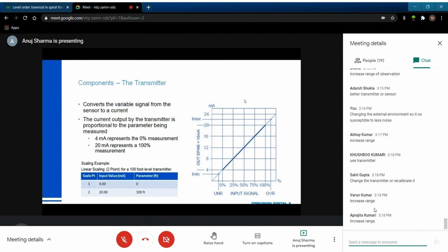In those conditions, most devices can be set up so that if you go over 20 milliamps, they set off these alarms, or if you go under 4 milliamps, they continue to display 0 and not go negative. So those over and under ranges are built into all of the devices that go into this 4 to 20 milliamp loop, and usually have different behaviors associated with them.